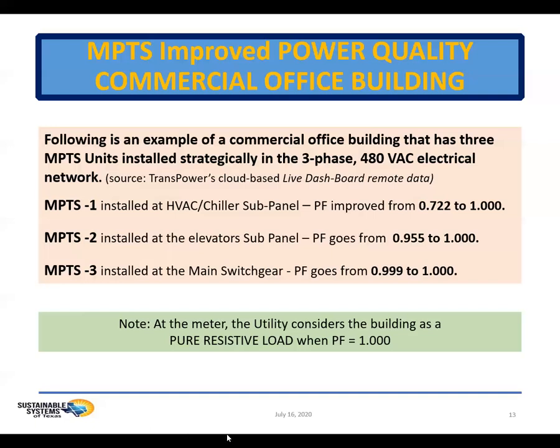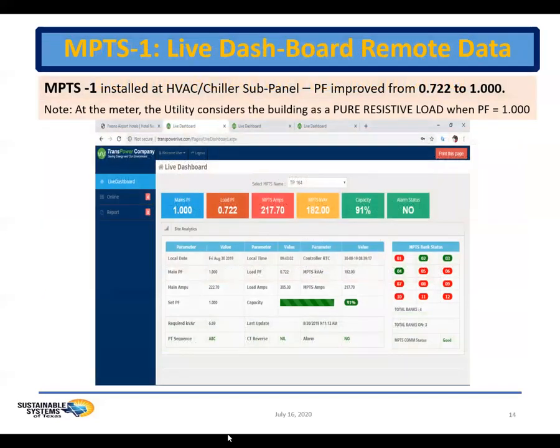So now we're going to look at MPTS number 1 dashboard. Here we see the snapshot of the dashboard, and it's recording a load power factor at 0.722. That's the second button on the top line. There are 4 banks on this system. 3 are online, indicating OK, as indicated by the green color on the right-hand side. The system capacity is at 91%, as noted in the second green button on the top left row.